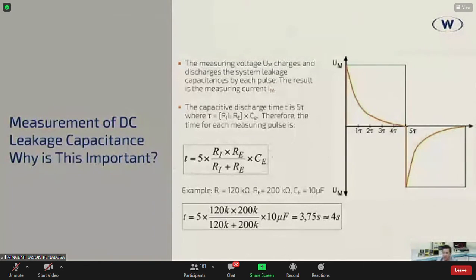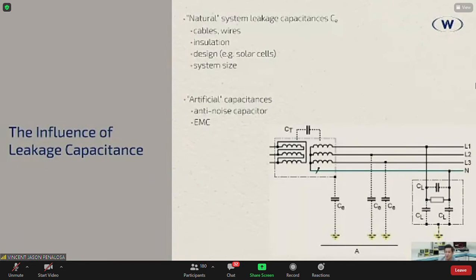So we have to be aware of that, especially for critical care units for hospitals. It is actually limited to 10 kVA. The isolation transformers cannot be more than 10 kVA. Why? Just because we go back to this, the natural system leakage capacitance, the system size. Because beyond 10 kVA, they've determined that leakage capacitance increases already. And in hospital care, in critical care units of hospitals, you need the measurements almost instantly.